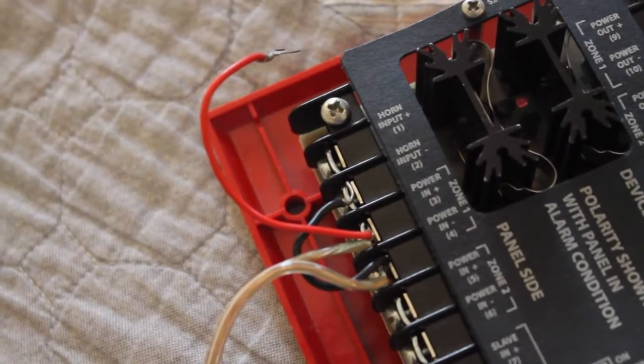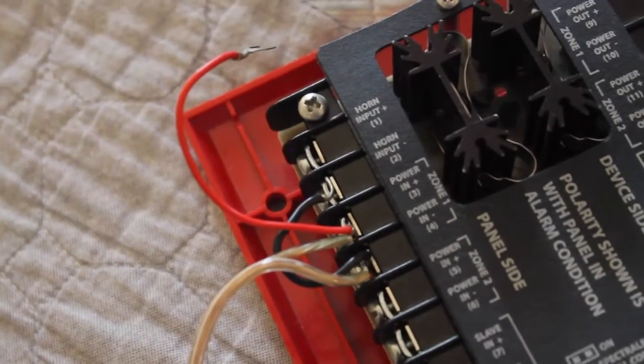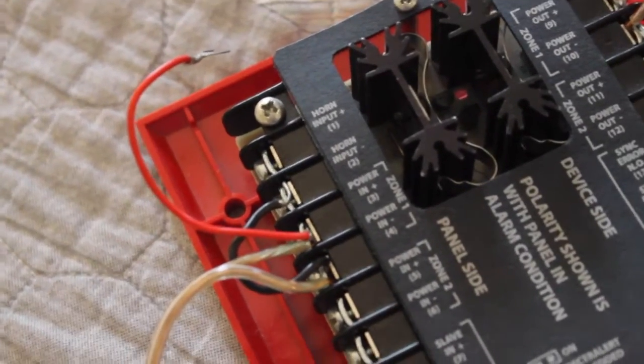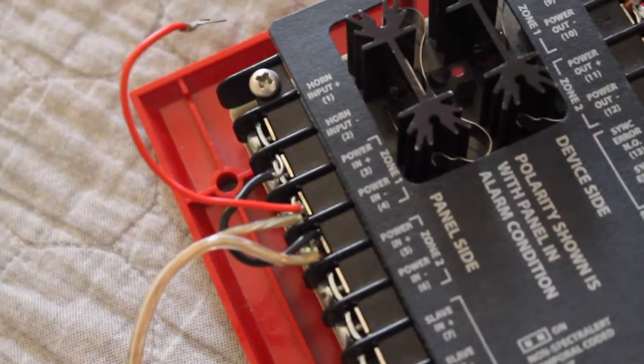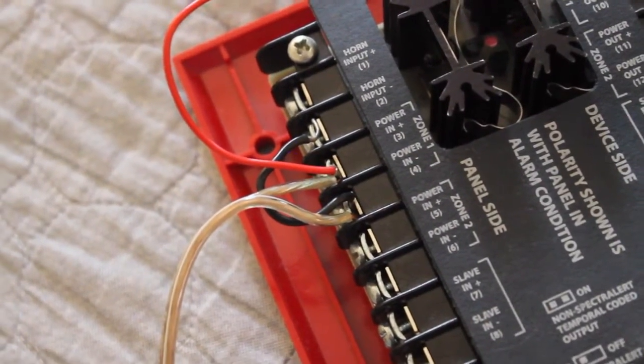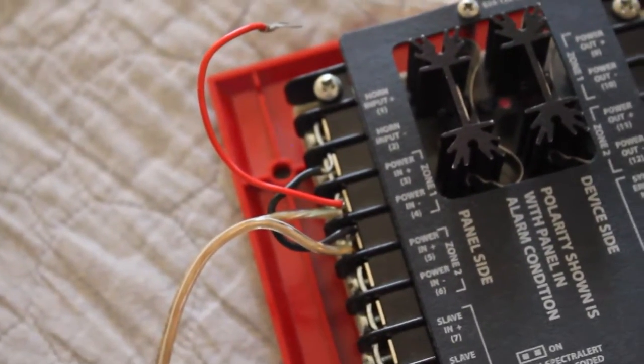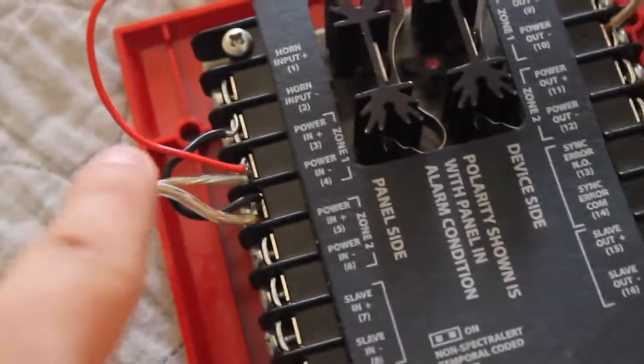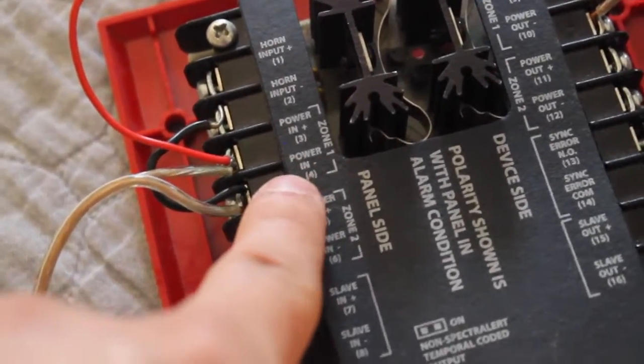So, I have a little bit of a treat here. I decided to remove the jumper wire between the horn input and the zone one input. On your typical four-wire panel, you would have the horn output, whatever NAC is controlling the horns, you would have it go into this input here, and then I think the strobes would just go into this input here.